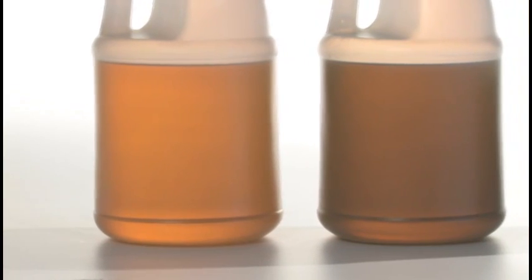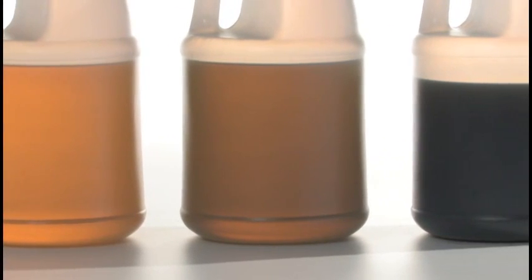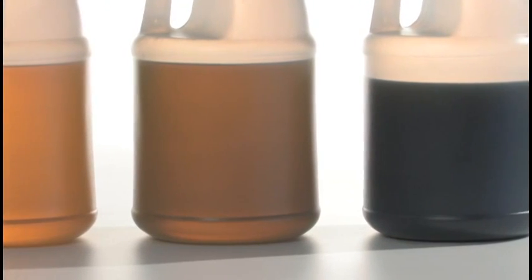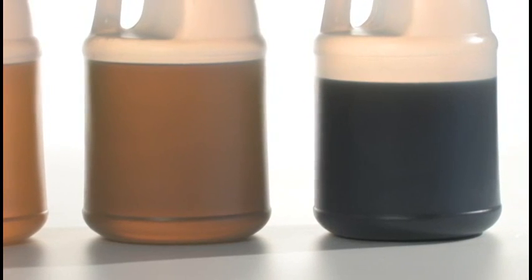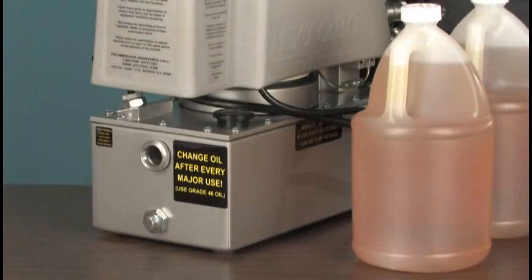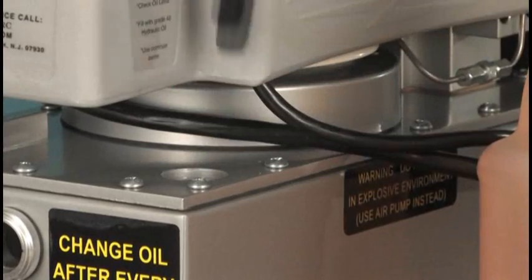As long as the oil is clear and amber colored it is probably okay, but if it has turned dark due to heat or cloudy due to dirt or humidity it should be changed immediately. There are no filters for you to maintain, but the single most important thing you can do to prolong the useful life of the pump is to change the oil as needed.